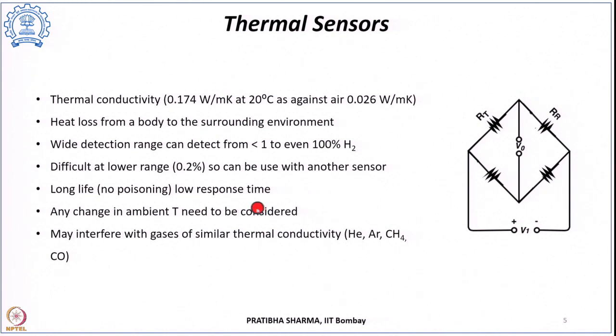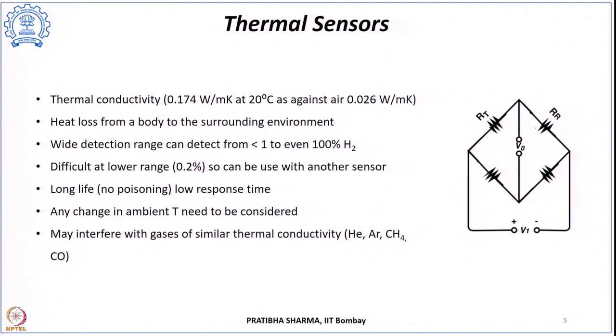The disadvantage is that any change in ambient temperature must be corrected for. Additionally, interference can occur from other gases with similar thermal conductivity to hydrogen, such as helium, argon, methane, or carbon monoxide, which is the major disadvantage of thermal sensors.